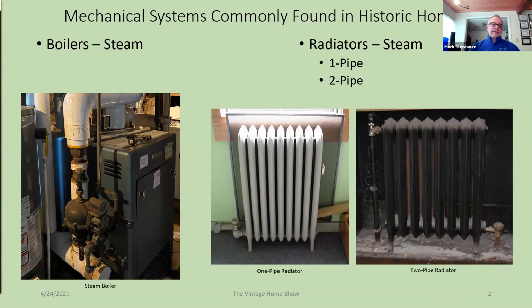The steam boiler, as advertised, turns water into steam, and then that steam is distributed around the house to typically radiators or other types of heat exchange equipment. You have single pipe radiators, which, as the name implies, have a radiator in the center with a single pipe connecting it, and usually an automatic air vent on the side. The way that works is the steam comes into the radiator, it displaces the air out that vent, and when that vent senses the steam, it shuts off, and so then the radiator heats up and condenses water.